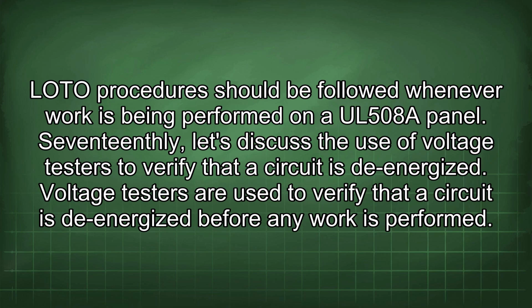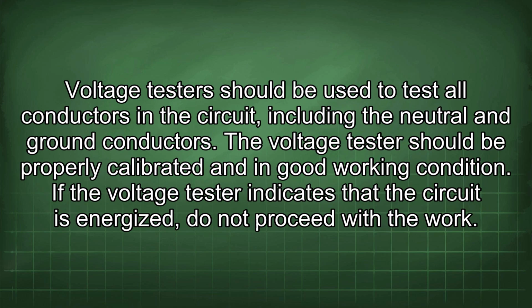Seventeenthly, let's discuss the use of voltage testers to verify that a circuit is de-energized. Voltage testers are used to verify that a circuit is de-energized before any work is performed. They should be used to test all conductors in the circuit, including the neutral and ground conductors. The voltage tester should be properly calibrated and in good working condition. If the voltage tester indicates that the circuit is energized, do not proceed with the work.